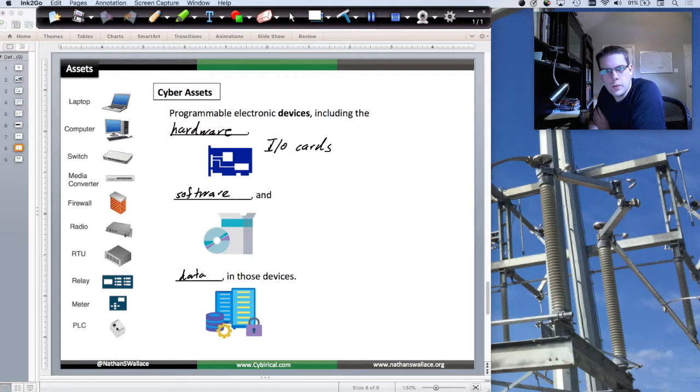We have the different, let's say, network cards that would also be added. So you have I/O as far as input output, contacts, right? Different data being brought in, different wires, and then you have the network card. So that's like all your communications. Let's say if it's a 61850 module, a Modbus module, DNP3 module, etc. And then you also have basically the ICs or integrated circuits. So you think about this. You got your CPU, you have your RAM.